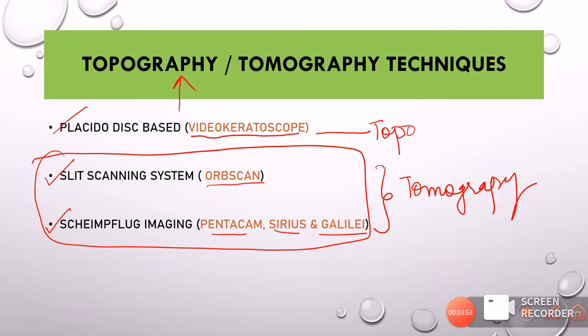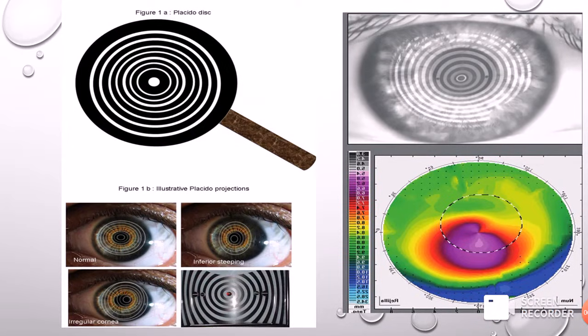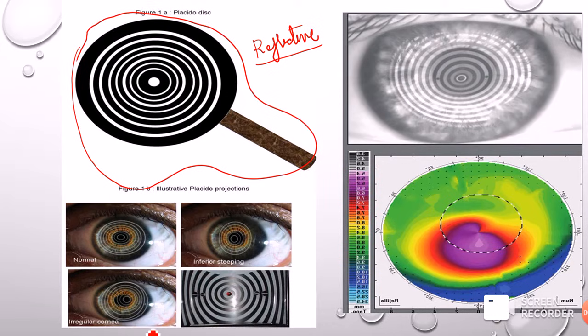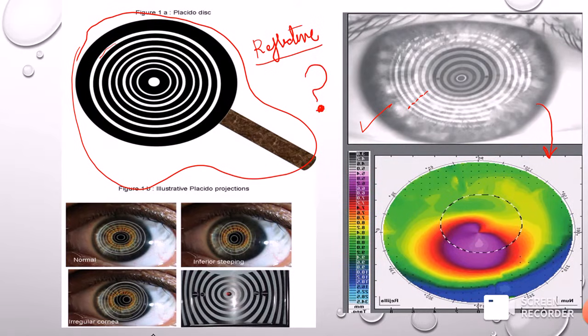The first technology is Placido imaging, the oldest technique in topography and tomography. It is a reflective technology. The video keratoscope has a device with concentric rings of alternating light and dark bands, and these rings are reflected onto the cornea. The image processing software then analyzes the distance between these rings in the reflection to deduce and make deductions about the anterior surface of the cornea.